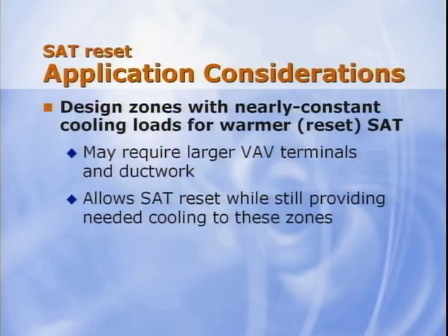For interior zones that will likely have near constant cooling loads during occupied periods, calculate design airflows for those zones based on the warmer reset supply air temperature. For our example, this would be 60 degrees Fahrenheit rather than 55 degrees. While this may require larger VAV terminals and ductwork, it allows supply air reset to be used during cooler weather and still provides the needed cooling for these weather-independent interior zones.